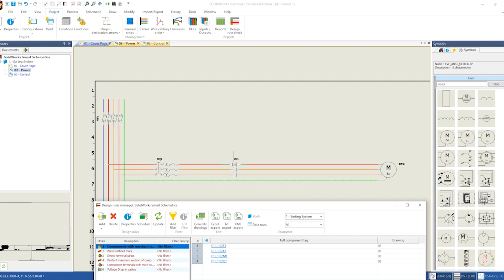So the system will also keep track of what components don't have a manufacturer's part that matches that circuit information. Here I've got a design rule check that says components missing manufacturer's parts. I've got one that says wires without marks - I didn't name my wires, so I didn't apply marks. I don't have any terminal strips, so I don't have anything that's empty.